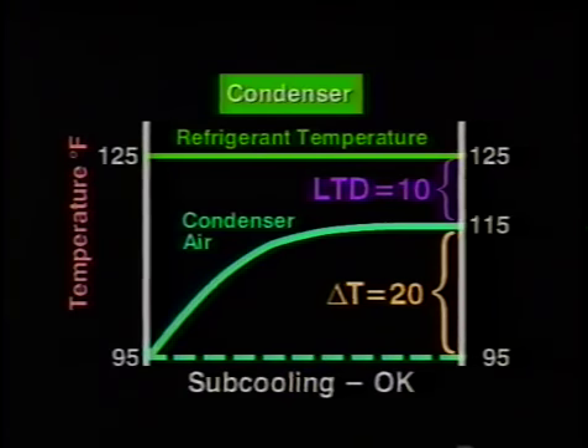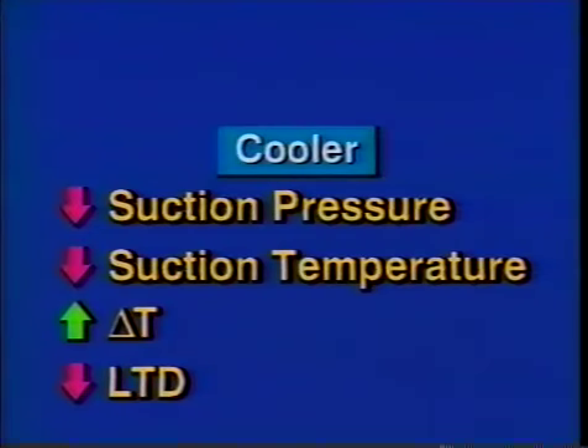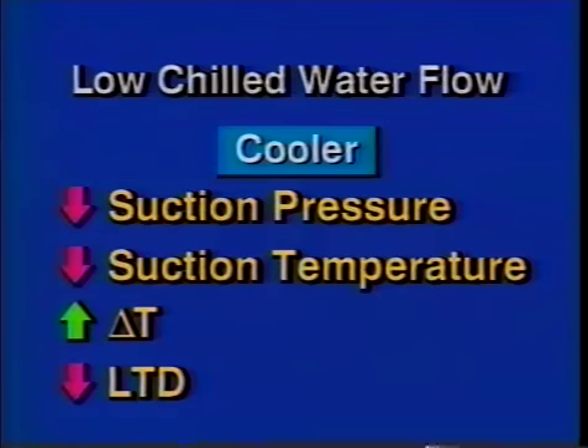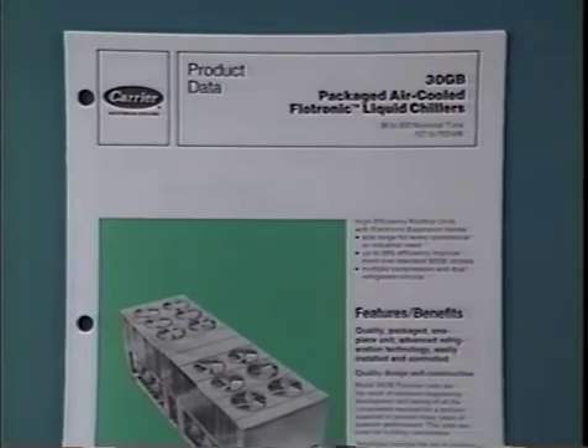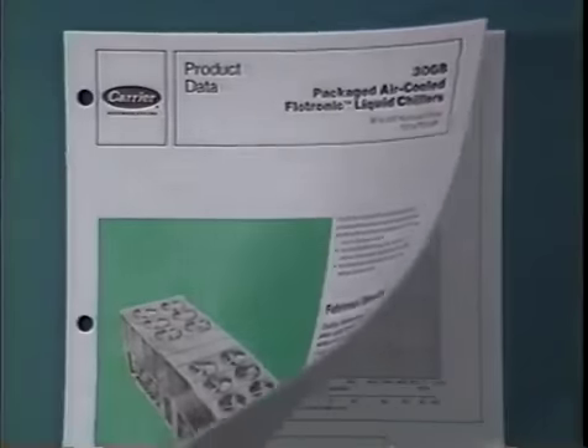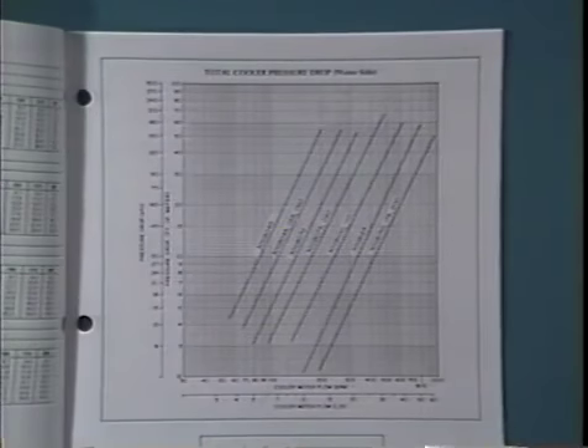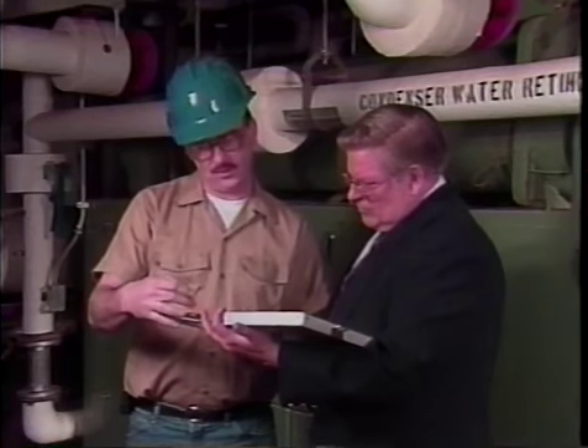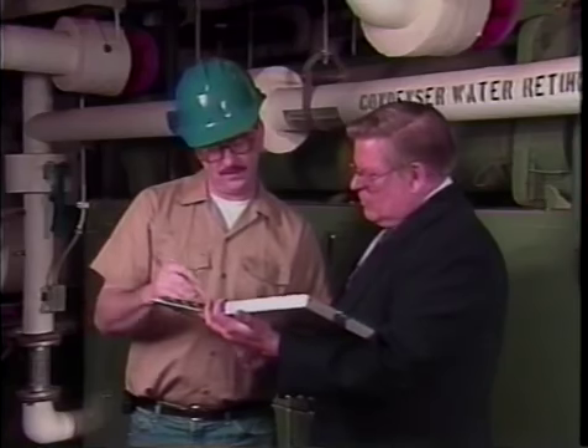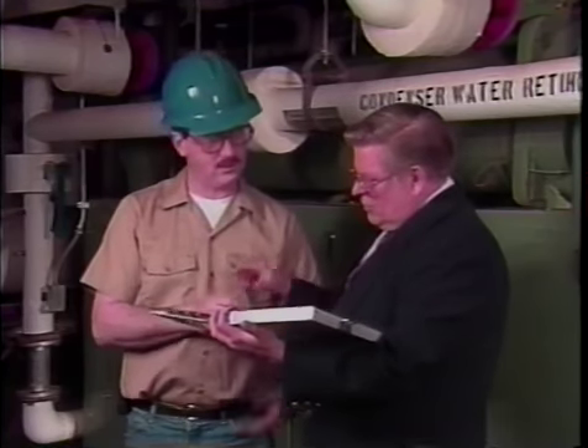So, turning our attention back to the cooler, we've seen that the saturated suction pressure and temperature are running low, the water side delta T is running high, and the LTD has decreased. The condenser is not fully loaded, and neither apparently is the cooler. Everything points to low chilled water flow as the problem. This can be verified by obtaining the water pressure drop across the cooler and referring to the manufacturer's product data as explained earlier in the program. You should now have a good idea on how to apply the log sheet data in determining what the problem may be on a reciprocating compressor chiller.